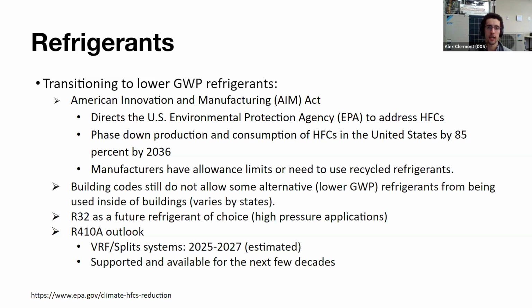One of the issues today is that the building codes do not allow the prime alternative for R410A yet if the refrigerant goes to occupied space. And this prime alternative for high pressure applications is R32. I mention high pressure because if you look at a water-cooled, cooling-only chiller, it's easier to get lower GWP refrigerants, as these are low and medium pressure refrigerants.